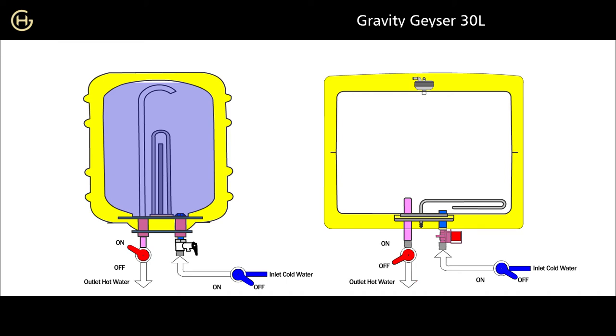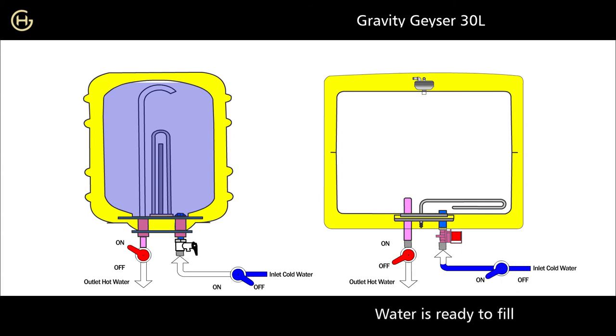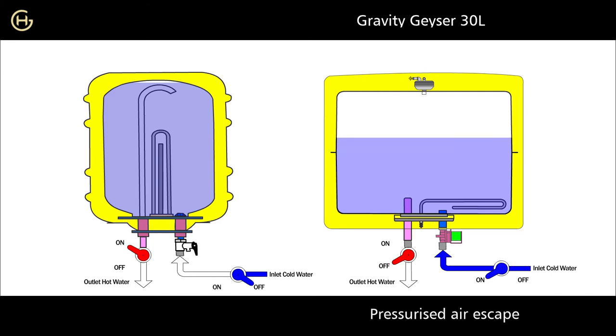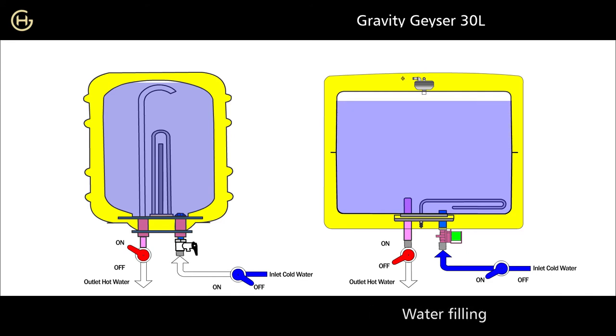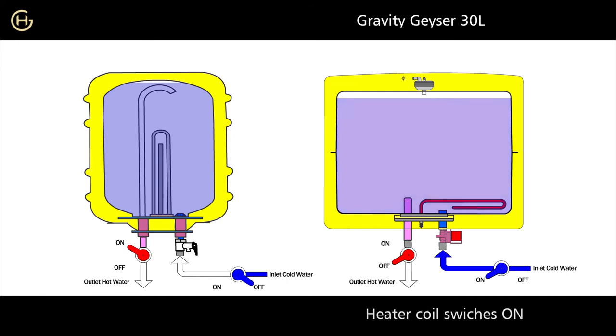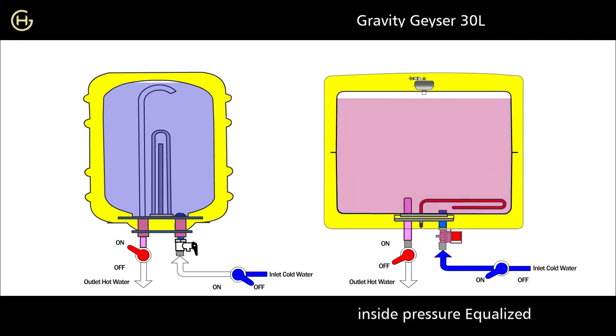In our gravity storage geyser, when the cold water tap opens, water is ready to fill. When the solenoid valve opens, even if the outlet hot water tap is closed, cold water flows inside the tank and pressurized air escapes through the pressure relief valve. The water is filled completely or partially as per user requirement. The solenoid valve then closes the inlet cold water for the set volume, the heater coil switches on and heats the water to the set temperature, and inside pressure is equalized to surrounding pressure.